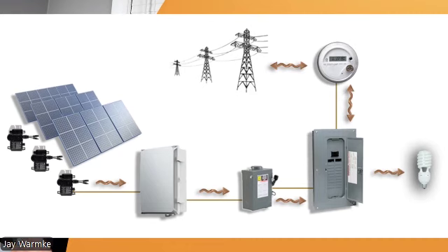The inverter has what's known as anti-islanding. So if it loses sight of the grid, it shuts down so that you're not feeding the grid when the grid is down. That creates a dangerous situation, and it's by law. You need to make sure you do that, or you need to disconnect your entire system from the grid before you're operating in a standalone mode.